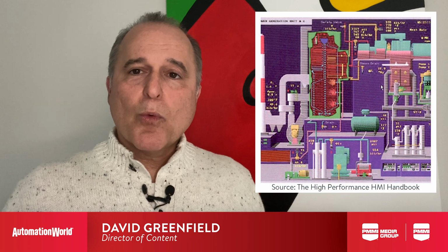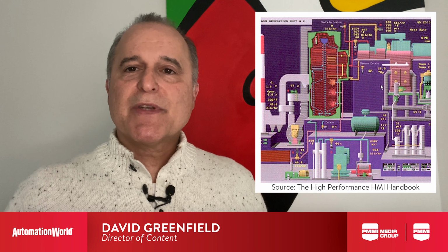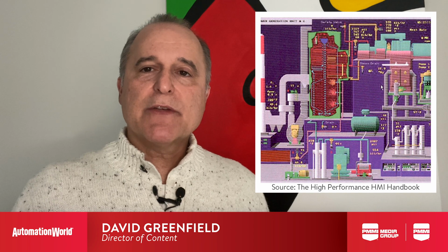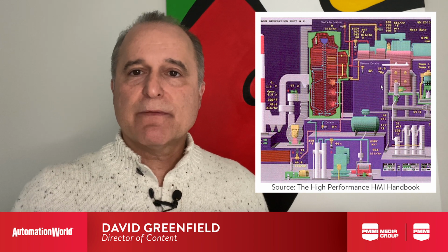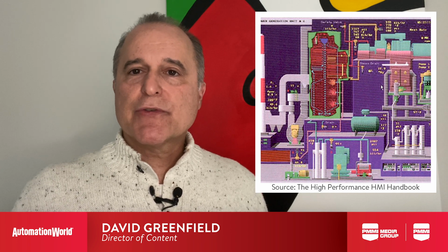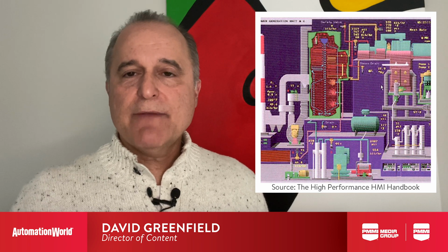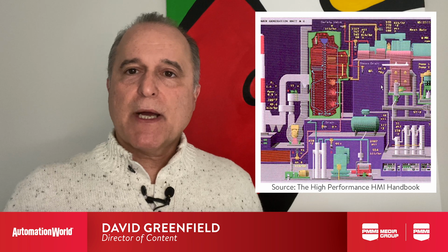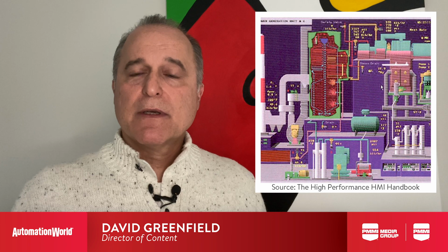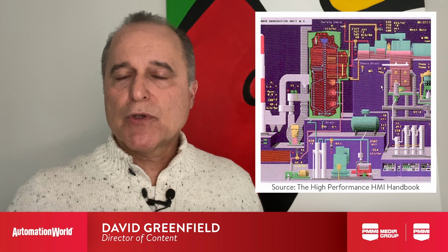Now, despite this, one of the main reasons for choosing a high-performance HMI are the data that show the potential downsides of the more colorful HMI displays. Investigative bodies such as the U.S. Chemical Safety and Hazard Investigation Board have identified the more colorful HMIs as causal factors in at least 3 refinery explosions. And a study commissioned by the U.S. Navy found that users of more simple HMIs outperformed users of the video game style HMIs by 70%, despite an overwhelming preference among the users for the more video game type of look with their HMIs.